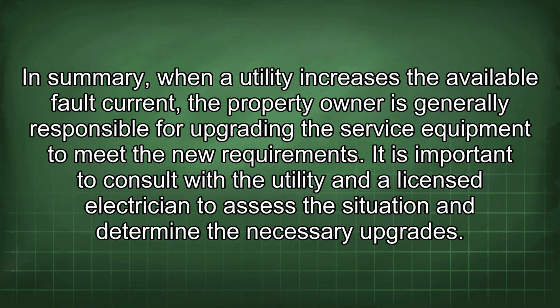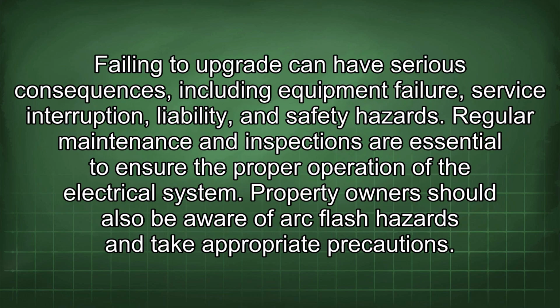In summary, when a utility increases the available fault current, the property owner is generally responsible for upgrading the service equipment to meet the new requirements. It is important to consult with the utility and a licensed electrician to assess the situation and determine the necessary upgrades. Failing to upgrade can have serious consequences, including equipment failure, service interruption, liability, and safety hazards.